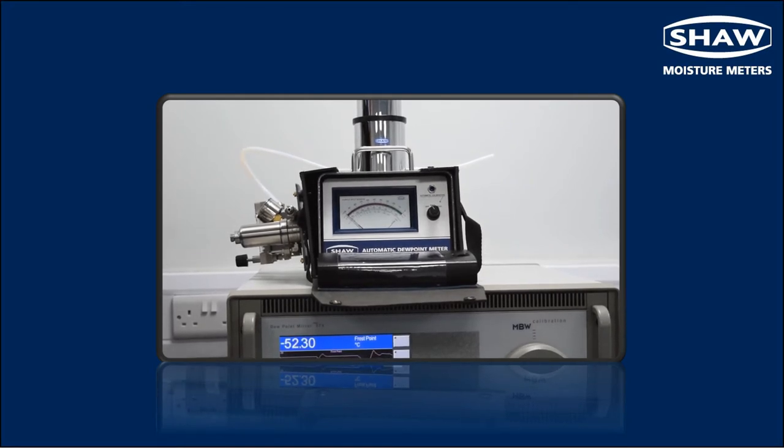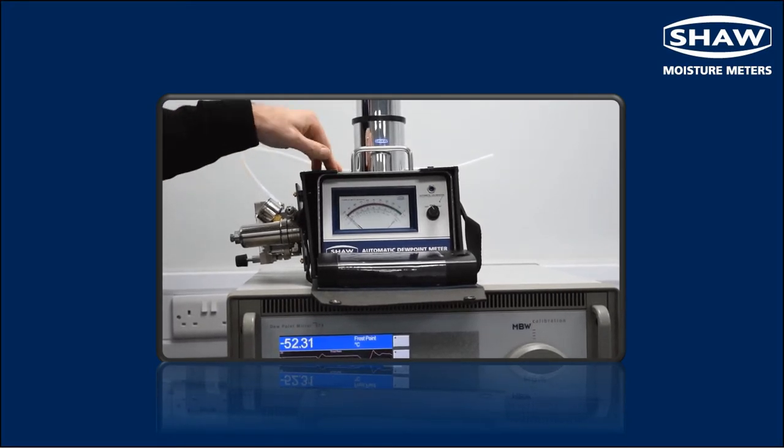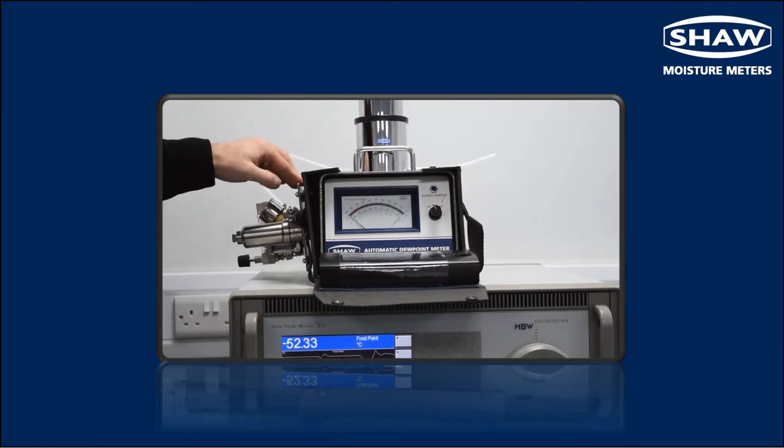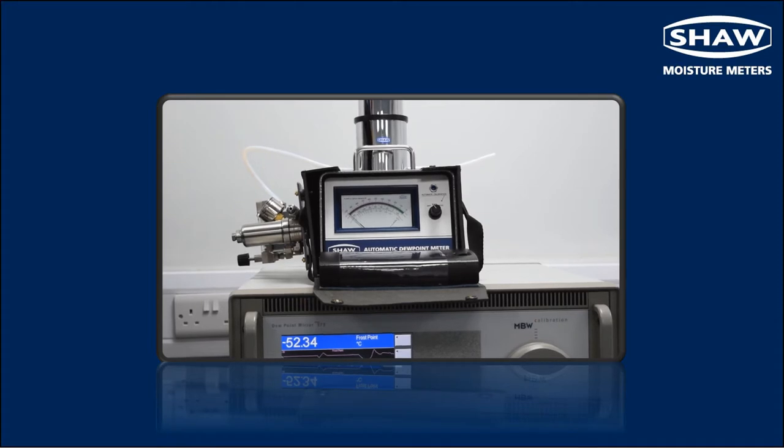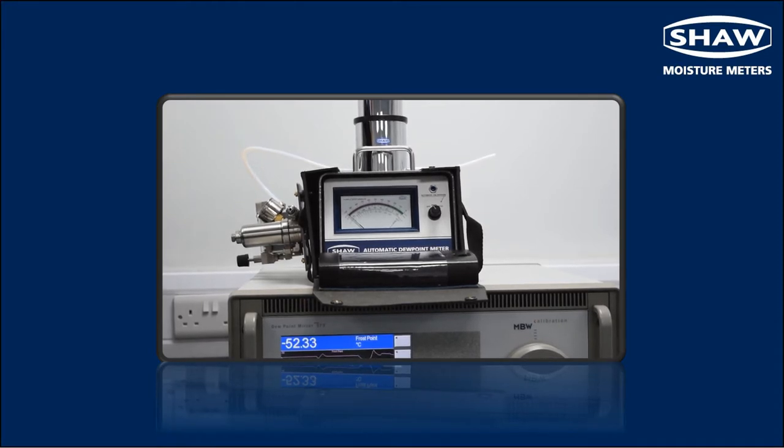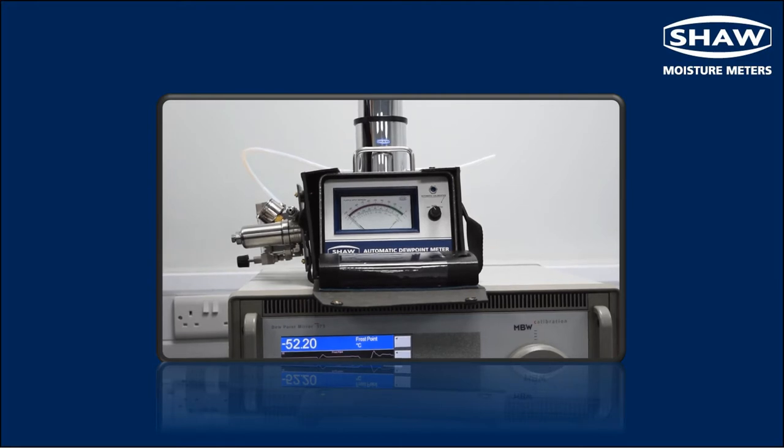Before we start using the SADP dew point meter with the SU3 sample panel, we first need to purge the system. So in industrial plants where sample lines are often isolated for long periods of time, it's important for us to purge those lines before we connect them to the SU3 sample system.